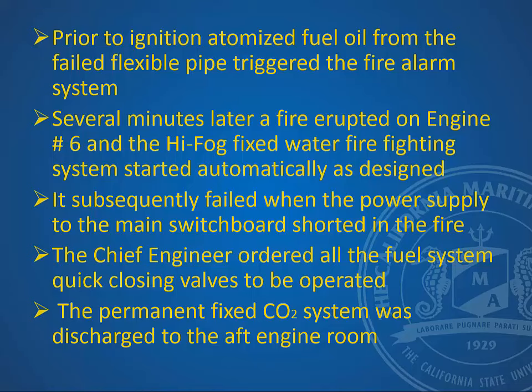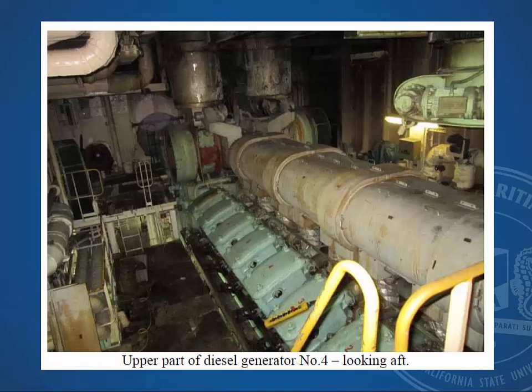The chief engineer had ordered all the fuel system quick closing valves to be operated to shut down the fuel to the fire, and the permanent fixed CO2 system was discharged into the aft engine room. That is actually what ended up putting the fire out.